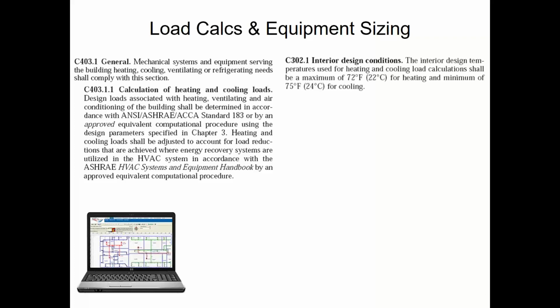When you do that, you oversize it more, which means they have to lower the set point more to get it to run long enough to dehumidify. It's a self-fulfilling prophecy. The more oversized the equipment is, the lower the cooling set point you have to set to get it to run. So if you size it smaller, it'll run long cycles at the 75 degrees and hence dehumidify. And if I can dehumidify well, all of a sudden 75 is very comfortable. Like I just told you, I keep my house at 77. I can't keep it at 75.